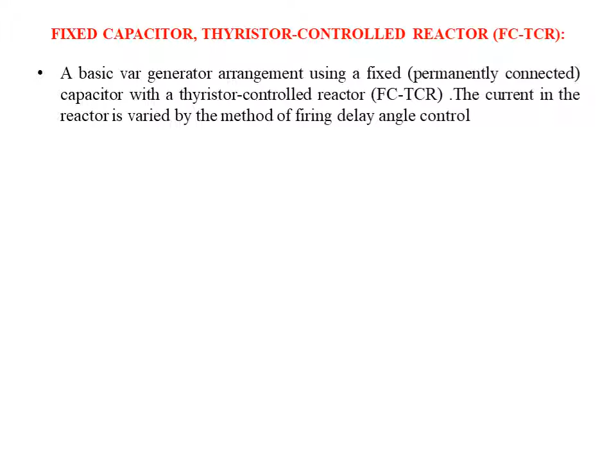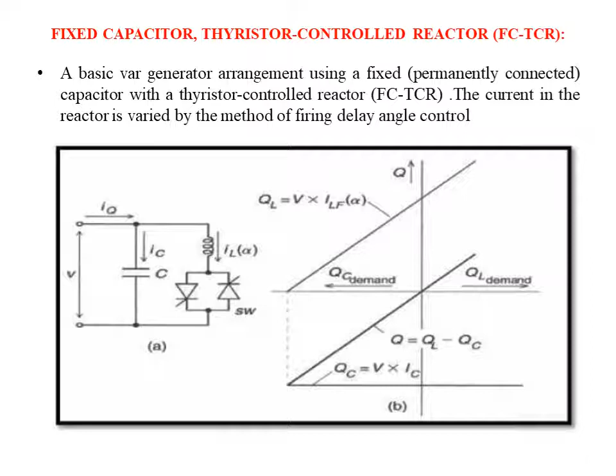So this is the basic diagram of fixed capacitor thyristor controlled reactor, where we have a fixed capacitor connected in shunt to back-to-back connected thyristors. You will see over here the thyristors are connected back-to-back having a gate signal, and by providing the delay angle or firing angle to the thyristors, we can have control over the current by varying the impedance. So what we basically do in this, by giving the firing angle, we mainly vary the impedance, and by changing the impedance we change the current in the system.